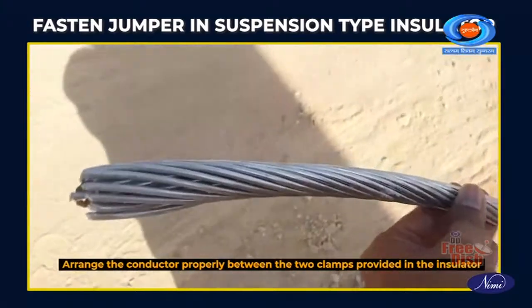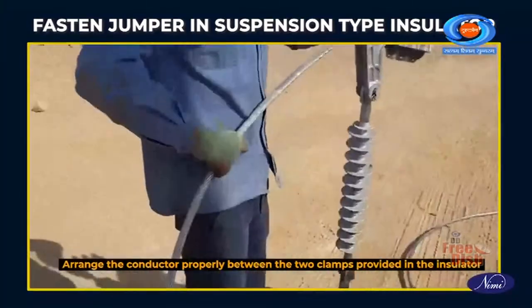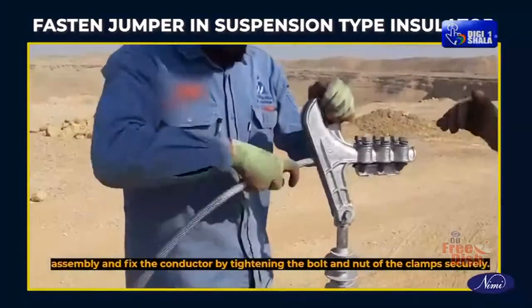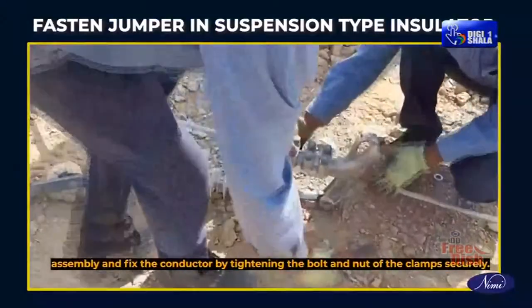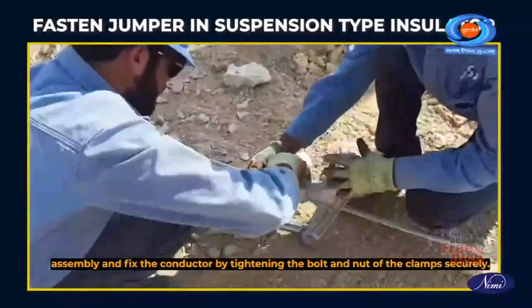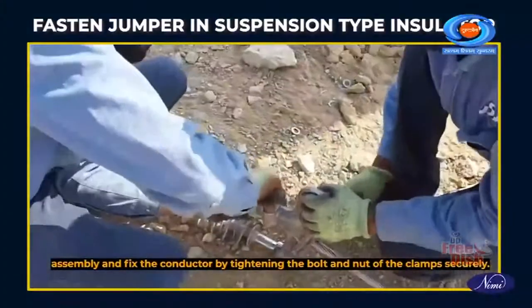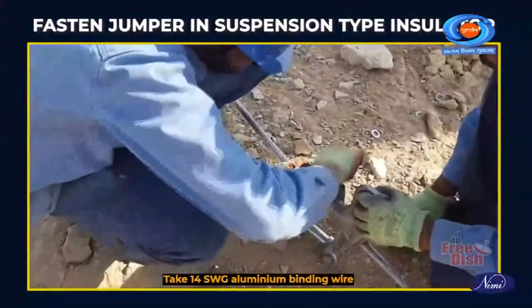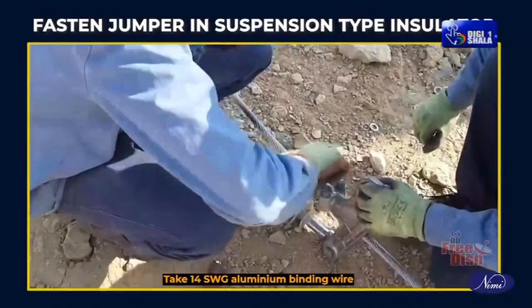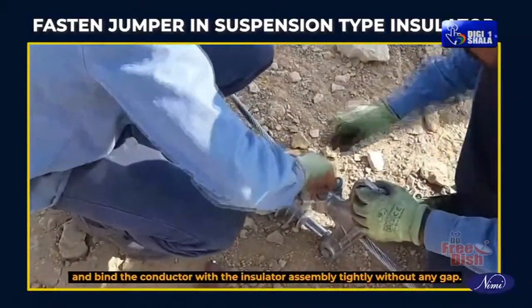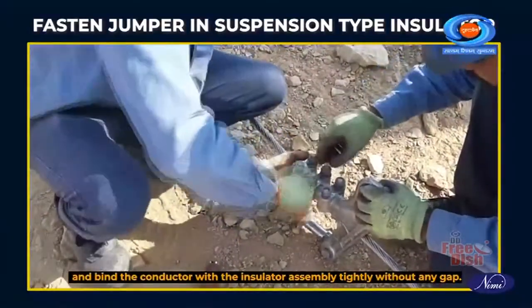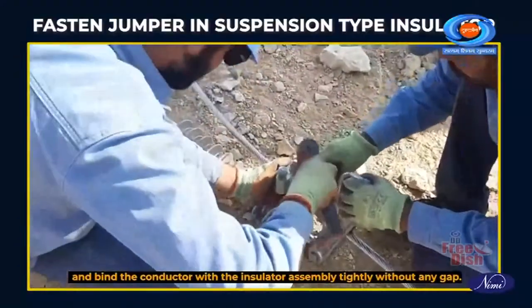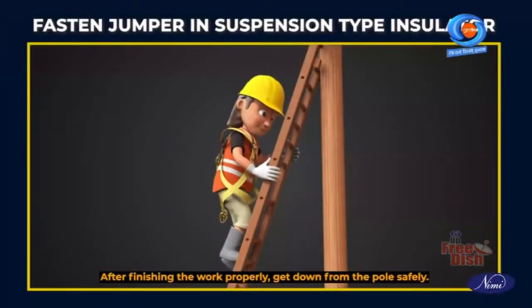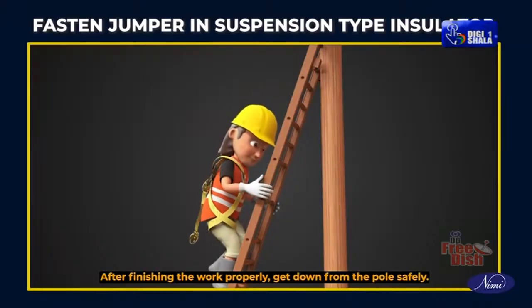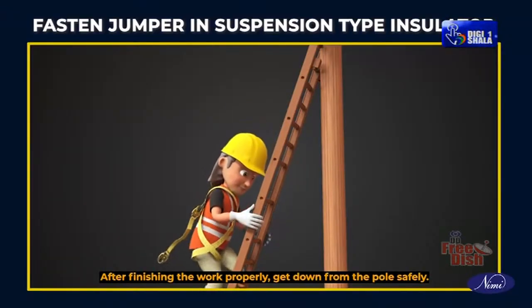Arrange the conductor properly between the two clamps provided in the insulator assembly and fix the conductor by tightening the bolt and nut of the clamps securely. Take 14 SWG aluminium binding wire and bind the conductor with the insulator assembly tightly without any gap. After finishing the work properly, get down from the pole safely.